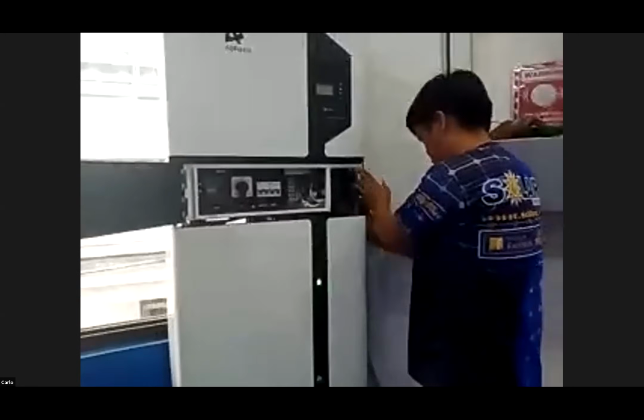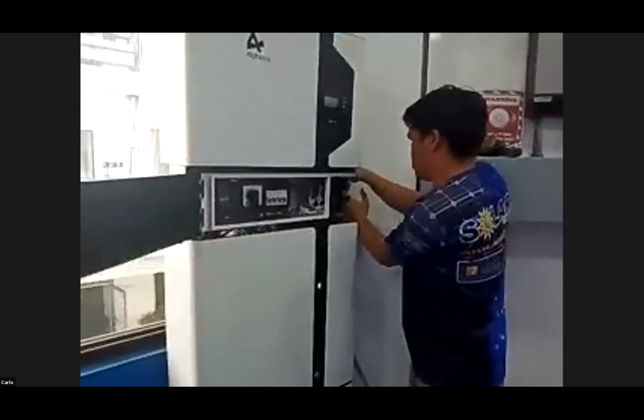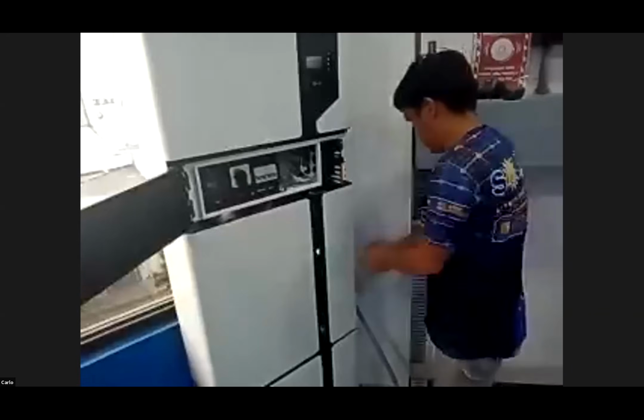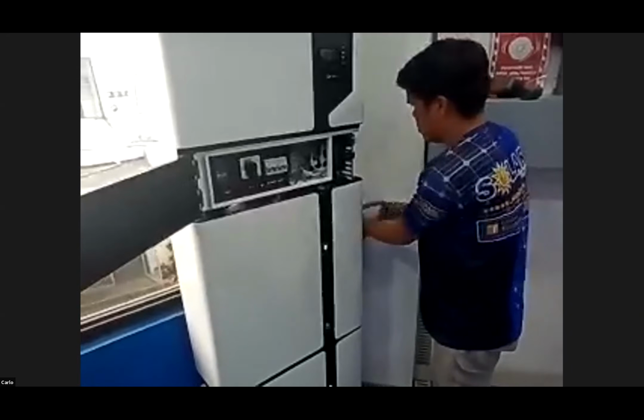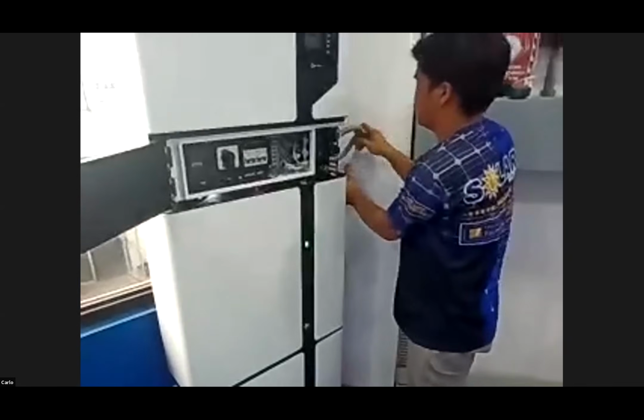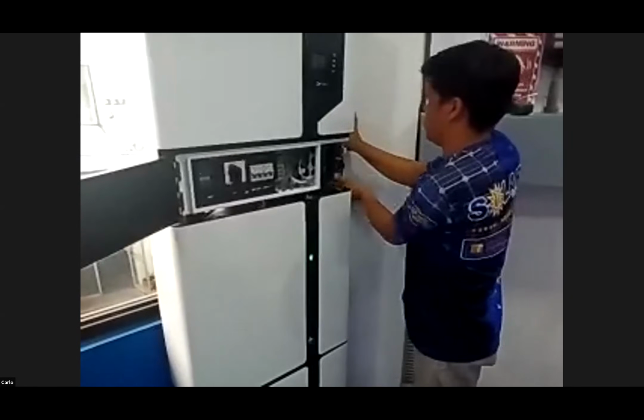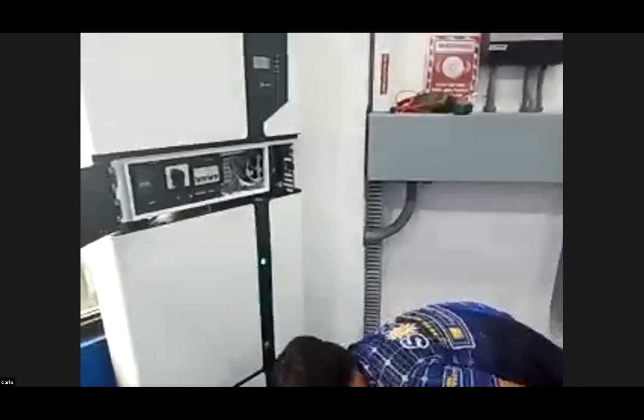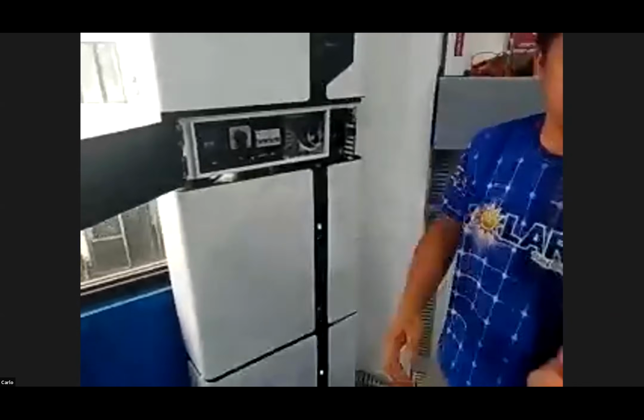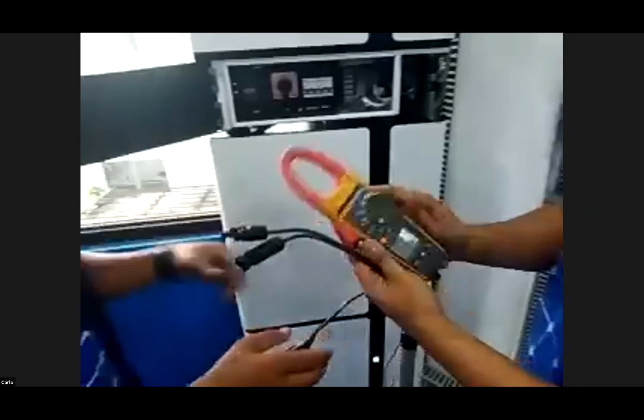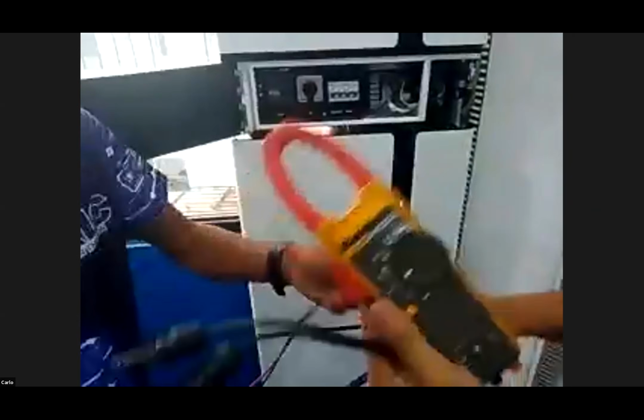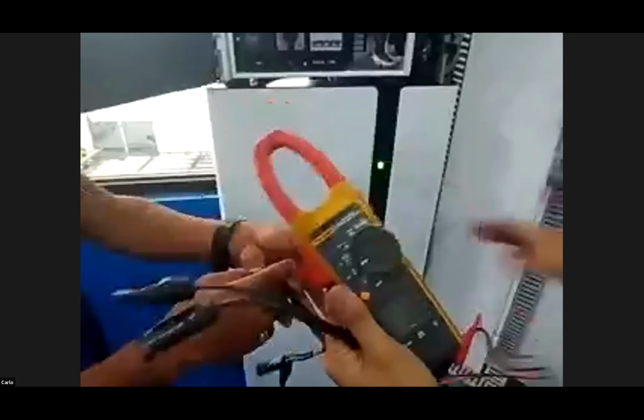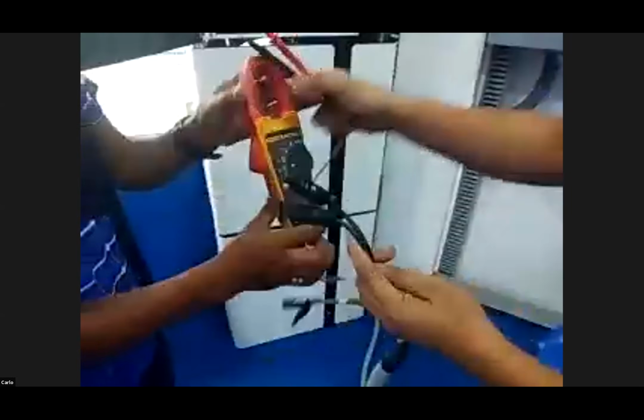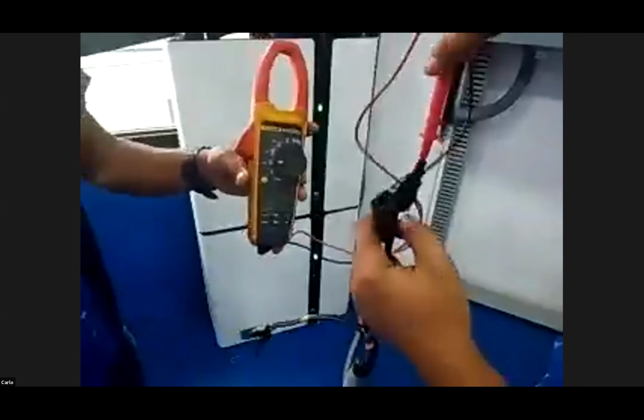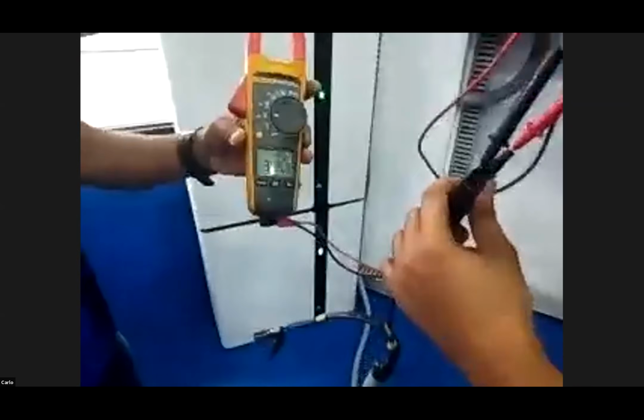Maybe this is a question for Kevin. Does the built-in PV disconnect switch also function as an overcurrent protection device or circuit breaker, or is it just a disconnect? Is it like a DC breaker or just an on-off switch, like an isolator? I think the answer, Ferdinand Santos, is that it's just like an isolator on-off. It does not have fault protection - it's more for manually disconnecting.